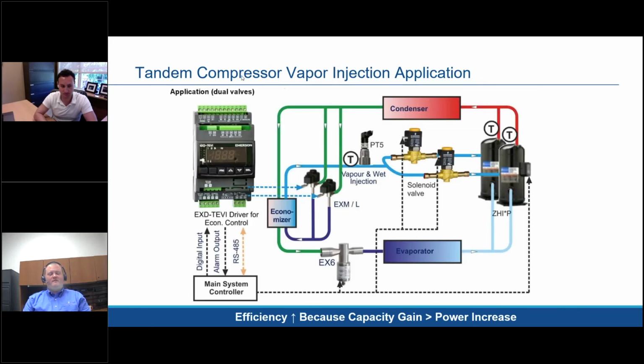Okay. So what's really controlling that mass flow is the controller. It can be the system controller, it can be our controller. And what that controller is trying to do is really control the discharge temperature of the compressors. So it's actually controlling the superheat going to those compressors. So the more cooling that's needed in the scrolls, typically the more mass flow you're going to get. And typically the more heating you need in the scrolls is the upper left side of the envelope, where you would want some of that additional capacity as well. So as you go farther and farther up on the left side of the envelope, you keep getting more and more capacity benefit for vapor injection versus a non-injection compressor. I think that's it. Okay.